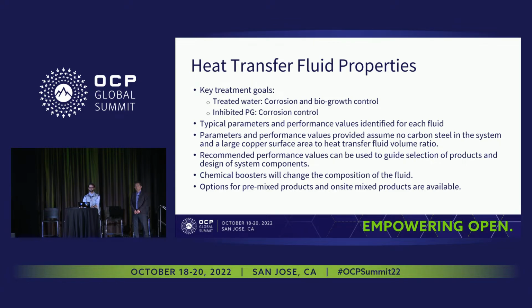Both of these fluids are going to require some consideration to manage corrosion in the system, while treated water is also going to require consideration to manage biogrowth. The two white papers outline recommended properties and parameters for each of these fluids, though actual properties may differ due to specific system design and treatment programs. All of the properties and parameters have been selected to minimize corrosion in the system and biogrowth.